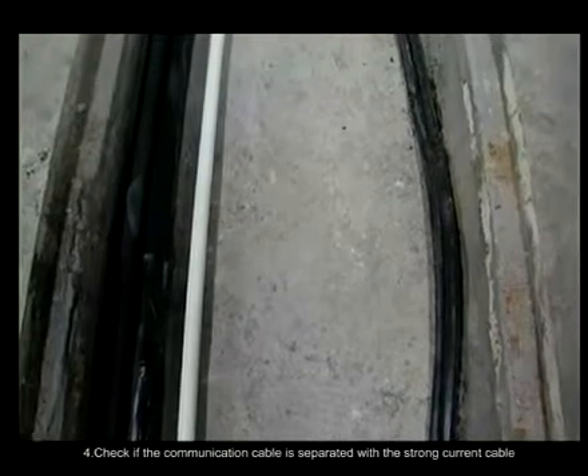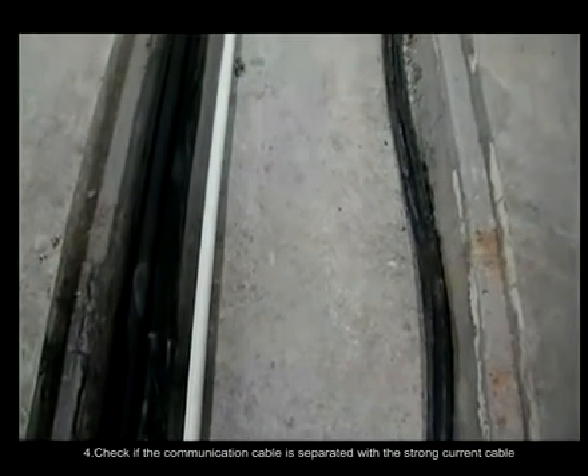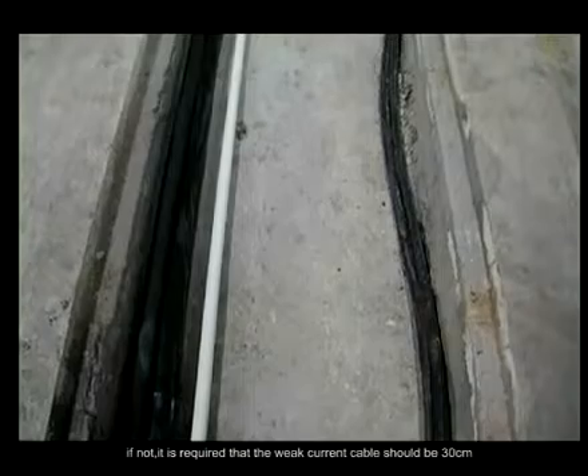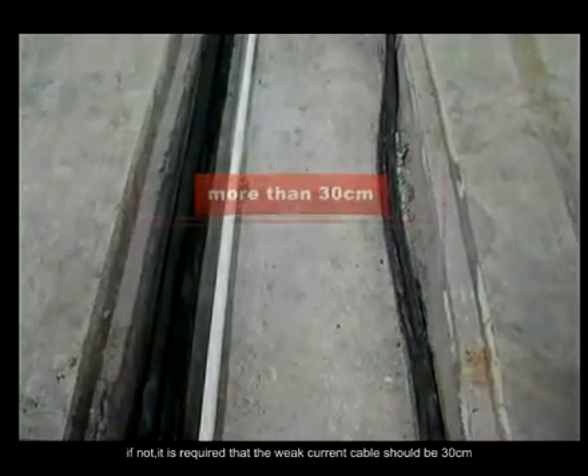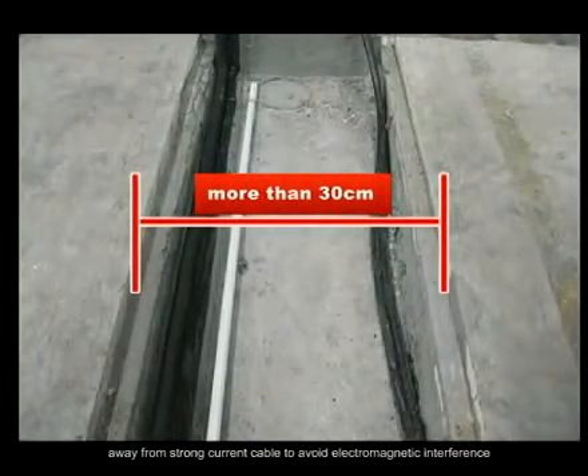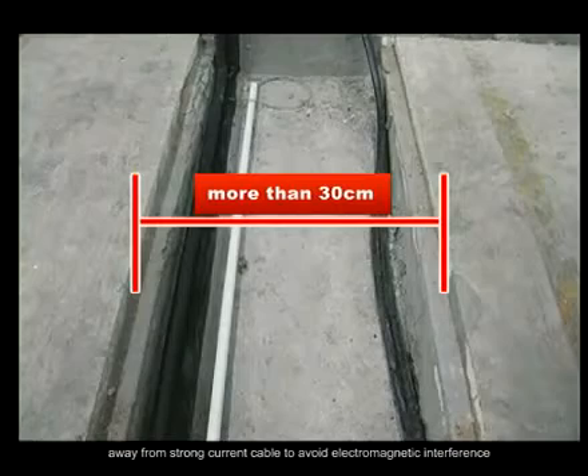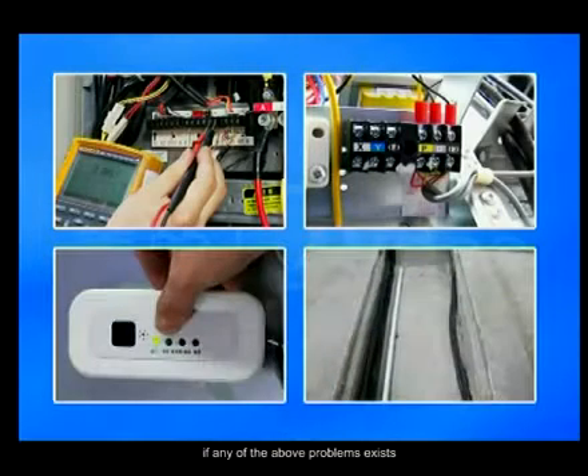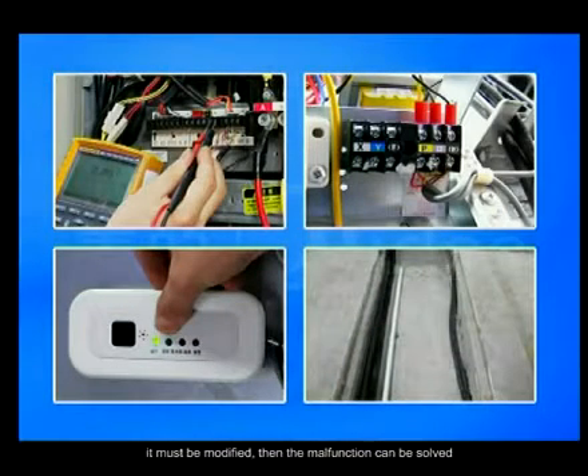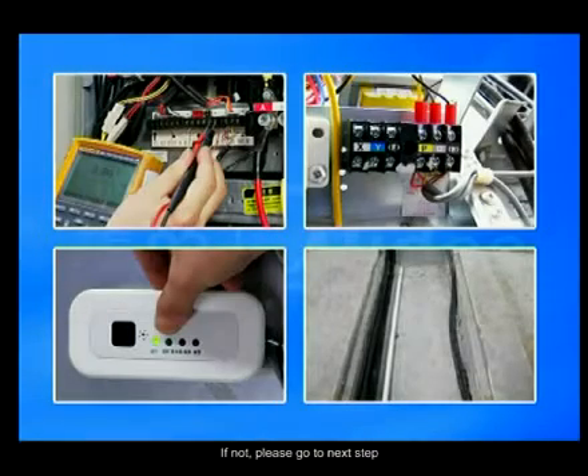4. Check if the communication cable is separated from a strong current cable. If not, the weak current cable should be 30 centimeters away from the strong current cable to avoid electromagnetic interference. If any of the above problems exist, it must be modified. Then the malfunction can be solved. If not, please go to the next step.